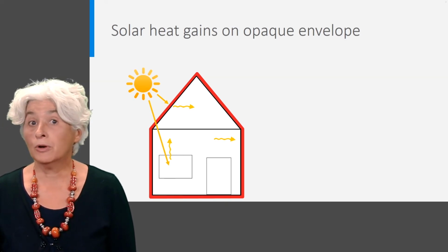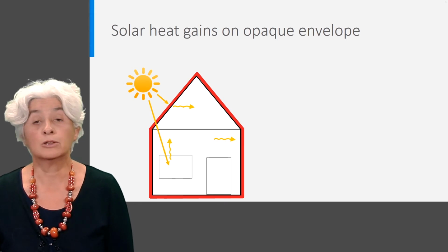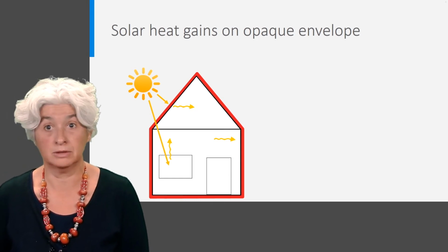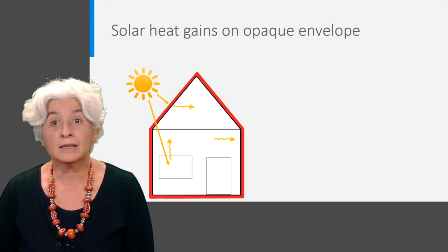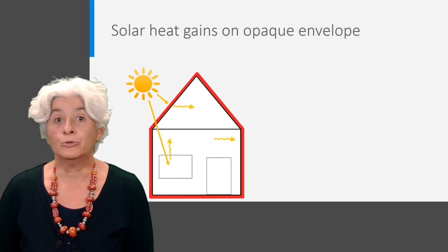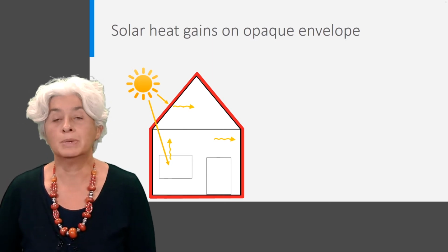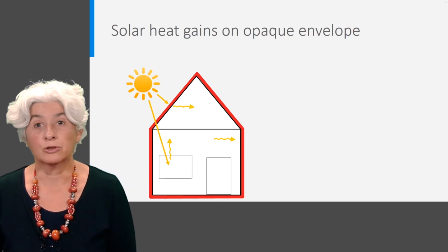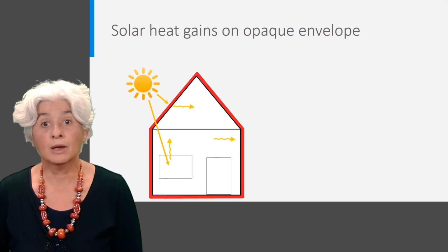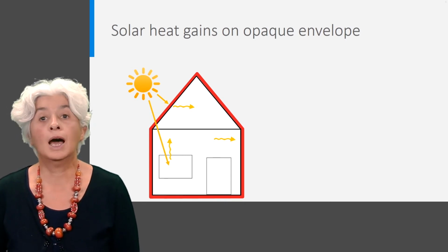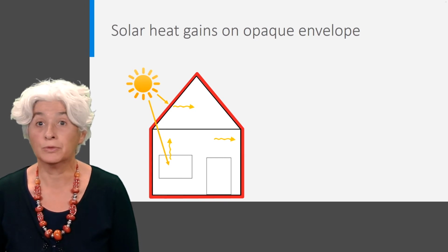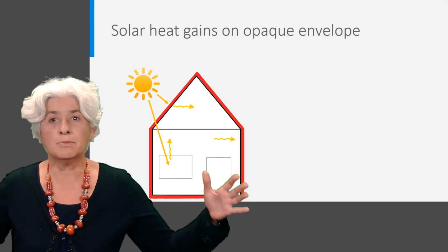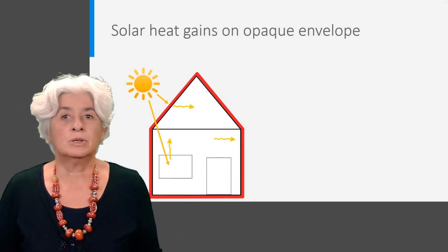Maybe you remember the first law of thermodynamics and that we said that we would neglect the heat stored in the construction itself when making the energy balance. The solar heat accumulated in the construction can come from outdoors or from indoors, from the solar radiation passing through the windows. Let's first look at the outdoor part of the construction. Neglecting heat storage means that we will neglect the heat accumulated in outdoor walls and roofs. In reasonably well-insulated buildings or buildings with thick, massive walls, this is a reasonable assumption.